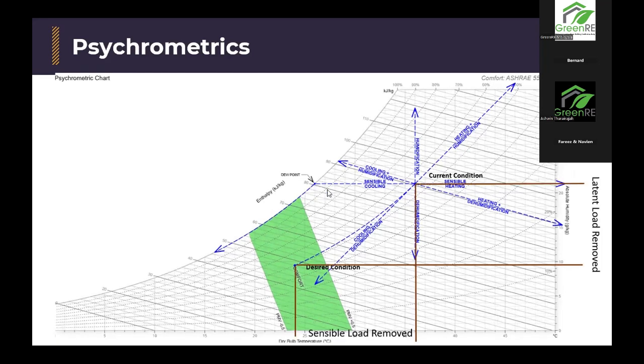Right, let me go here. Like I said, in a detailed calculation, you won't be referring to any table and determining, oh, what is my sensible coil ratio? You will be using this data right here. You will calculate your latent load based on this data. I'll show you examples of formulas shortly. You will take the value here: what's my absolute humidity value here? What's my absolute humidity value here? You'll plug it into a formula, and that will tell you this is my latent load. And then you will do the same for your sensible load.